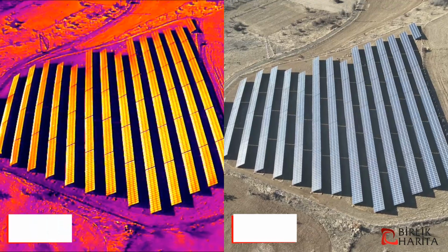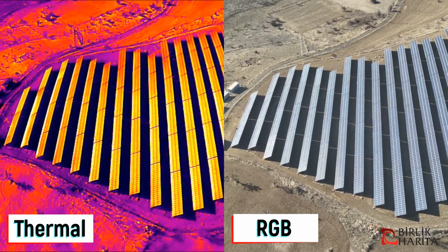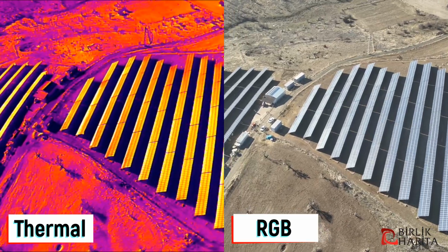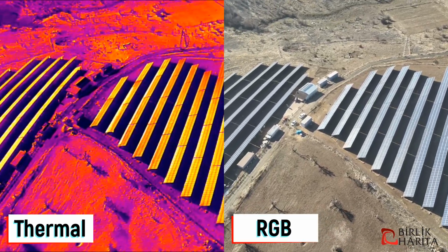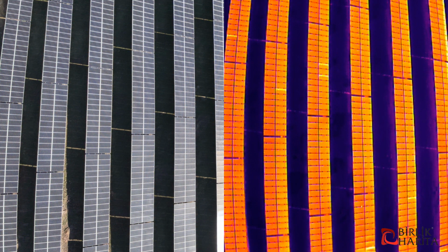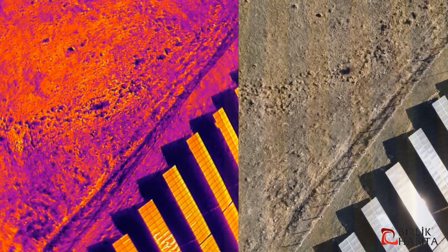Our thermographic measurements are made with dual sensors to enable appropriate analysis. Each thermal anomaly will have a detailed list of properties, including anomaly type, anomaly cause, delta temperature, remedial action, and much more. During our analysis, RGB and thermal images are matched to increase accuracy.